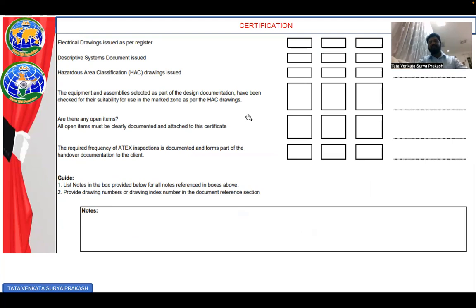Every facility we work in has a hazardous area classification. That is your quick guide to plan your emergency response. For example, within one facility there are different hazardous area classifications, with different fire zones given. The purpose is to identify which area to isolate if anything happens, only to limit the impact. This gives you an immediate guide to plan your emergency response, to prevent a small incident from exaggerating into a catastrophe, and to help guide and protect your systems and processes.